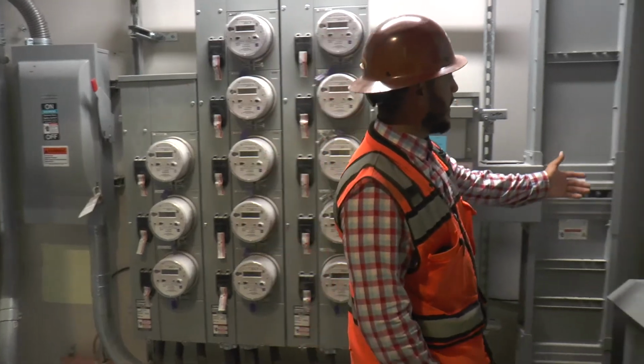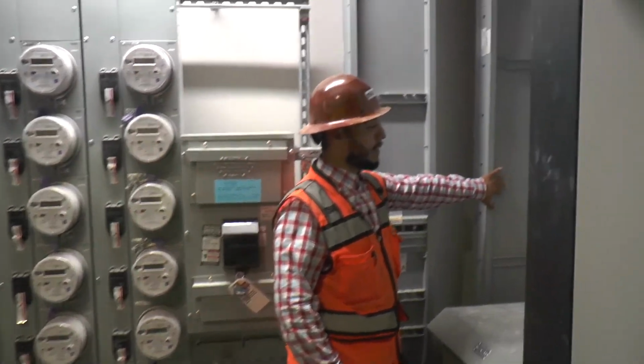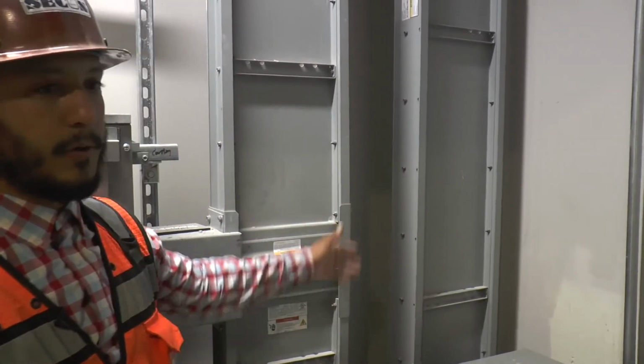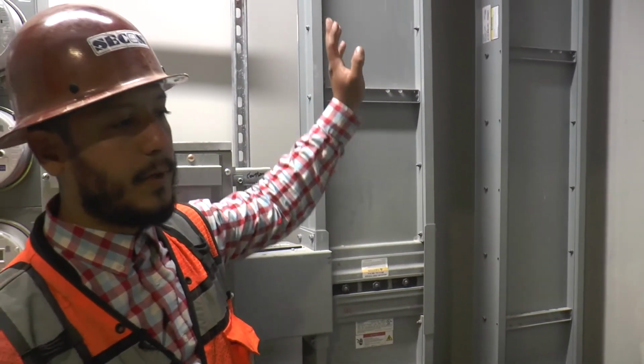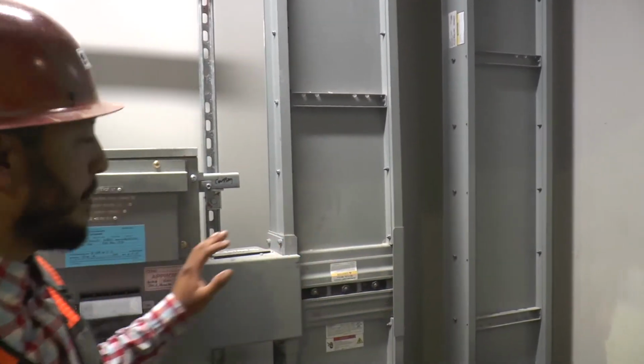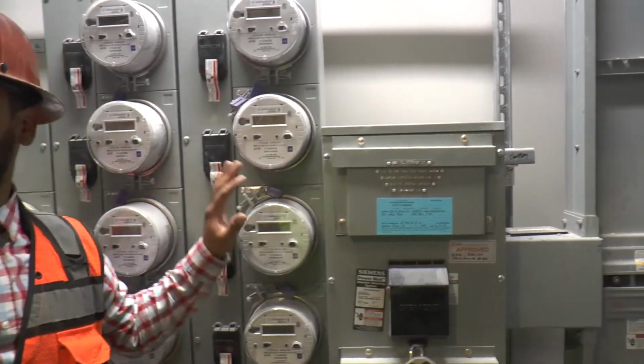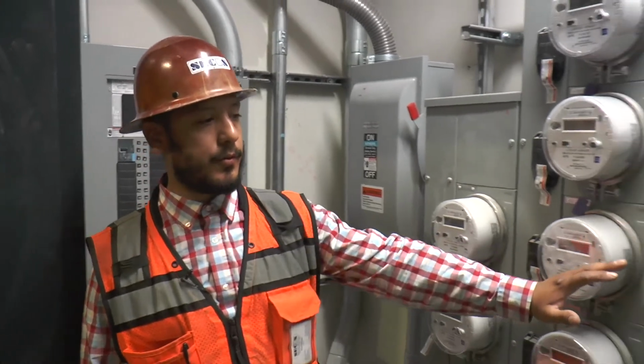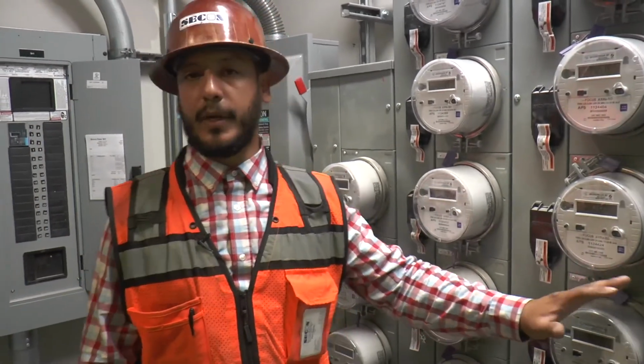Over here is the switchboard 3 bus run, which will feed the upper floors. This is just a continuation through the floors. And once we get to 19, you'll start seeing the same tap off, power mod, and meter section. All of this distribution is 208, excuse me.